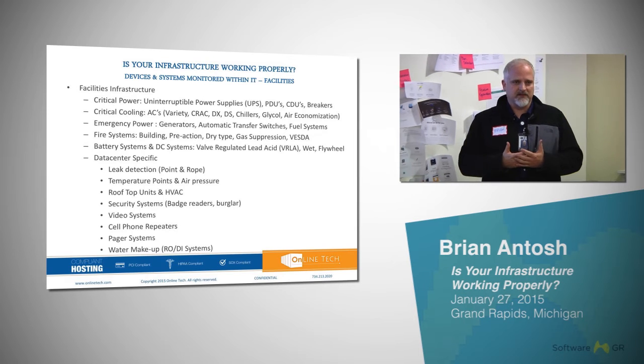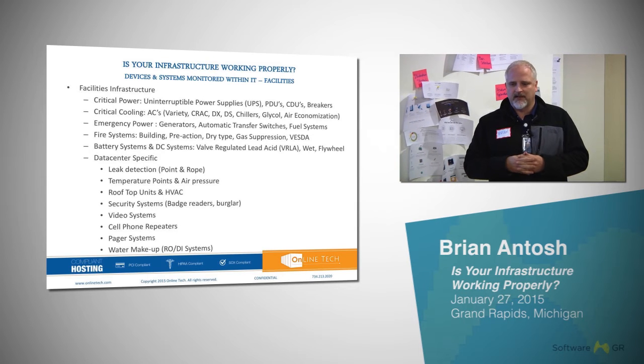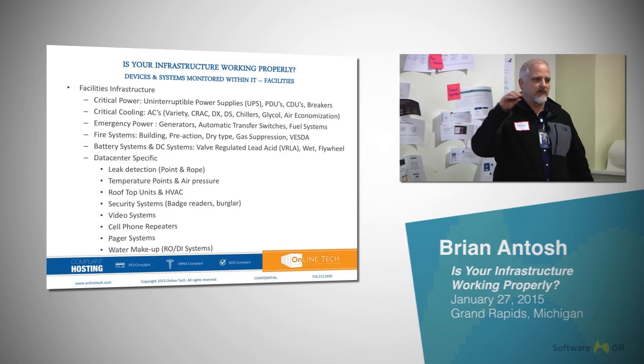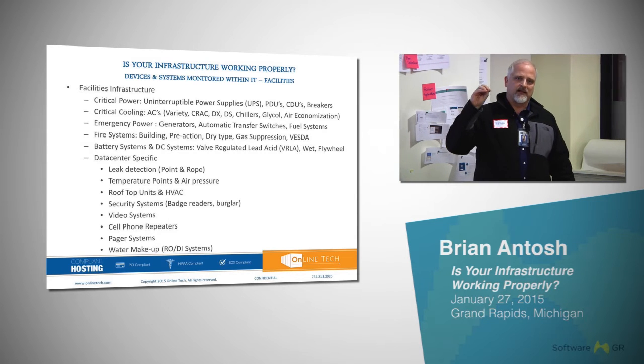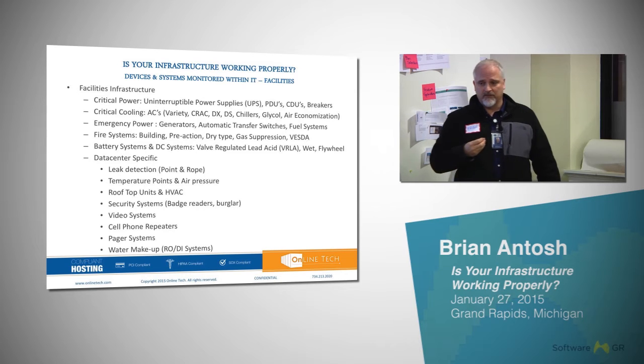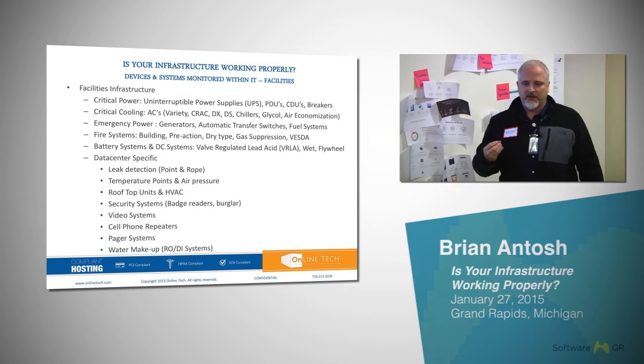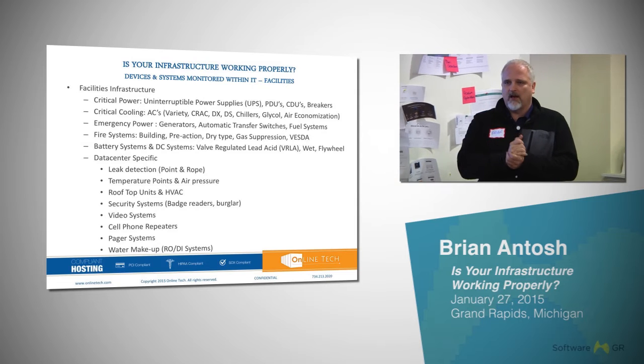And then you have sniffer systems called VESDA. I don't know what VESDA actually stands for, but it's an air sampling system, and it's so sensitive it can start to pick up burning electronics before even a dog could smell it. So that's on the front end of trying to figure out if something's wrong before it actually happens, and trying to find out what's going on.